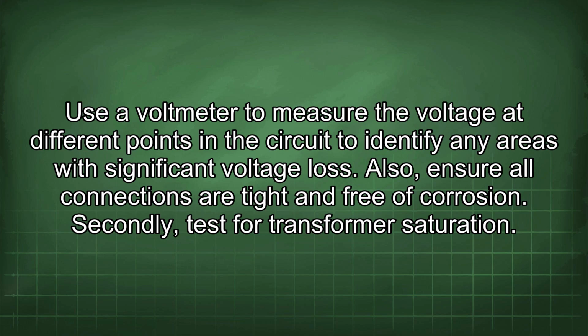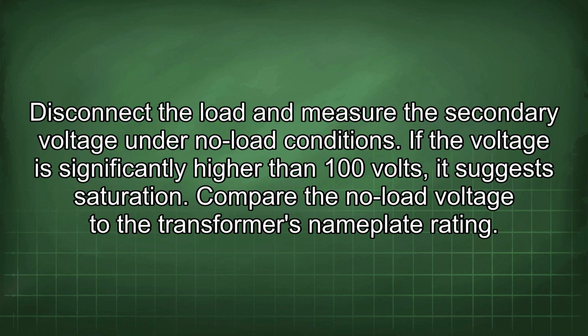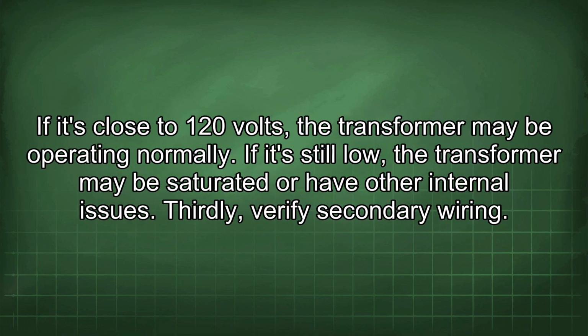Secondly, test for transformer saturation. Disconnect the load and measure the secondary voltage under no load conditions. If the voltage is significantly higher than 100 volts, it suggests saturation. Compare the no-load voltage to the transformer's nameplate rating. If it's close to 120 volts, the transformer may be operating normally. If it's still low, the transformer may be saturated or have other internal issues.